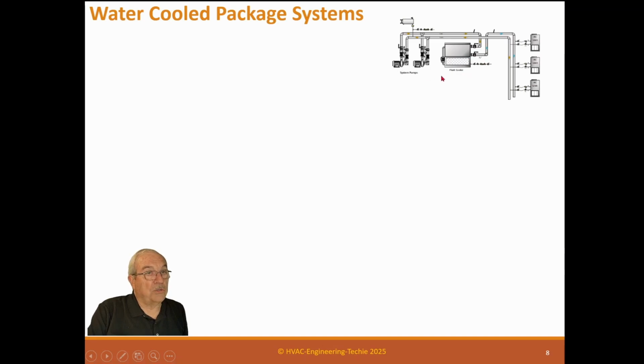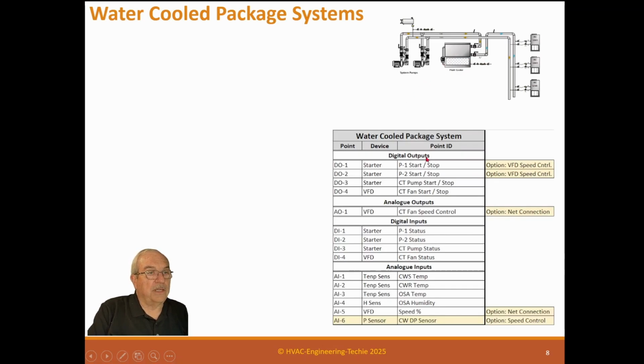So we have more control points because we have to run this pump and this fan. And here's a point list for that. The point list is we have a digital output for the P1 pump. We have a digital output for P2 to start those pumps. We have a DO3 for the cooling tower pump, this pump to run this fluid cooler. And then we have a VFD to run this cooling tower fan, start-stop.